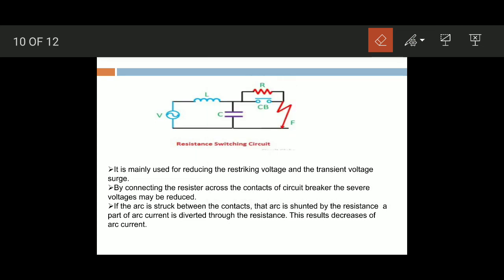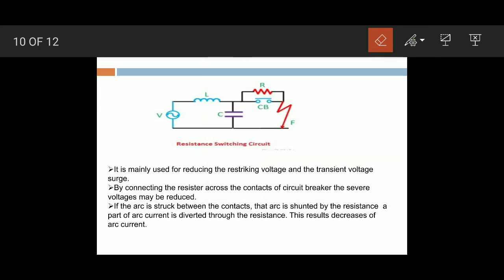When the fault occurs, the contacts of the circuit breaker open and an arc is struck between these contacts. With the arc shunted by the resistor, a part of the arc current is diverted through the resistance. The result is that the arc current decreases and the rate of deionization of the arc increases.